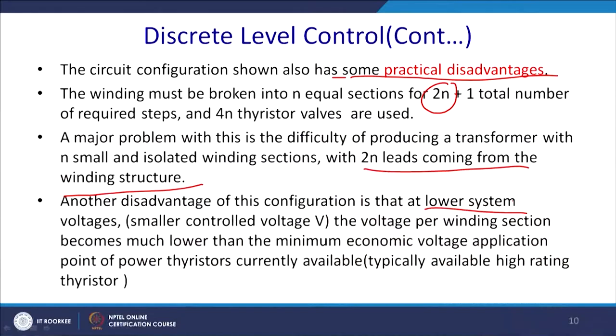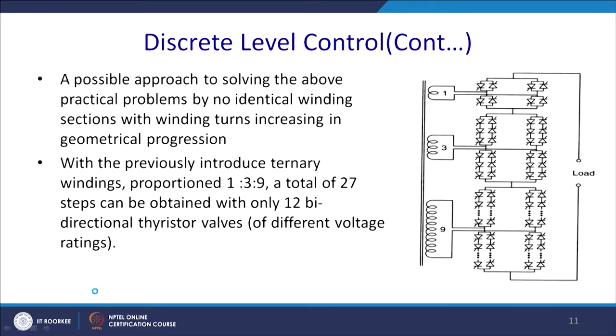Another disadvantage of this configuration is that at lower system voltage, with smaller control voltage V, the voltage per winding section becomes much lower than the minimum economic voltage for the typically available power rating of thyristors. So, a possible approach to solve the above practical problem is to use non-identical winding sections with winding turns increasing in a geometrical progression. That is what we have shown in the previous slide.